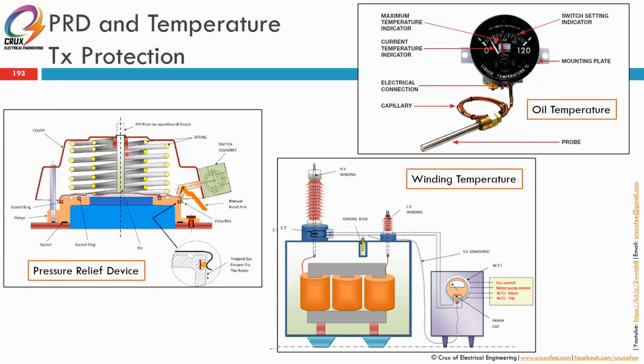So this pressure relief device is maybe rated to a certain, maybe 3.5 bar or something. So if the pressure within the transformer tank is built up to more than that pressure, this pressure relief device will relieve the pressure within the transformer tank. And the spring will pull the PRD back to its original position. But there's a switch here to indicate whether the PRD has operated or not. Okay.